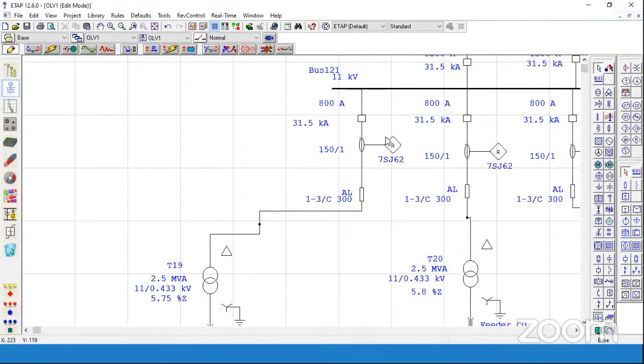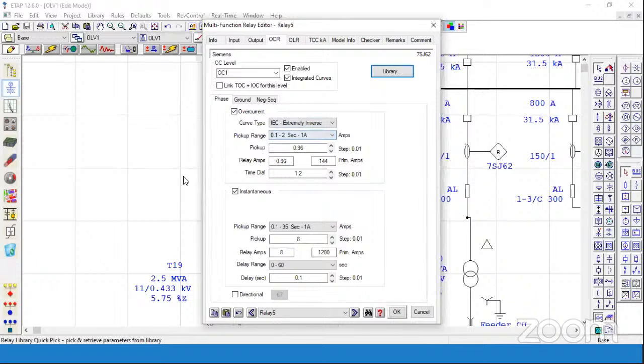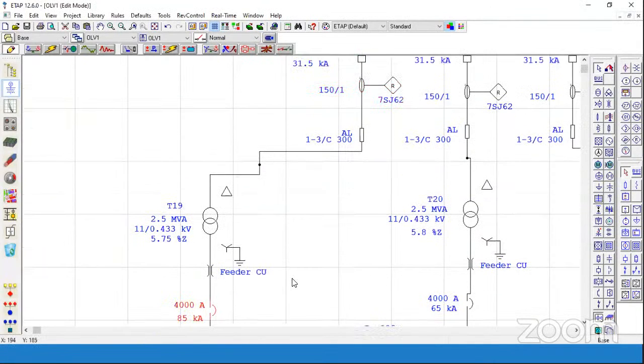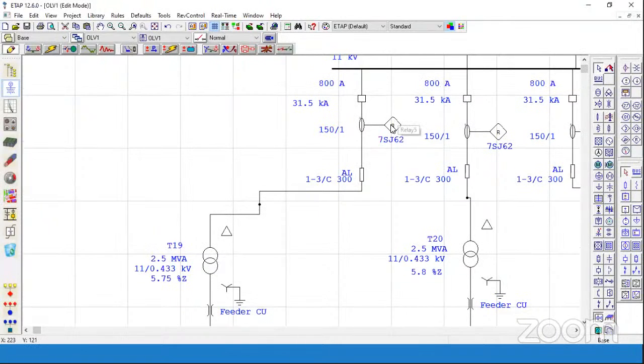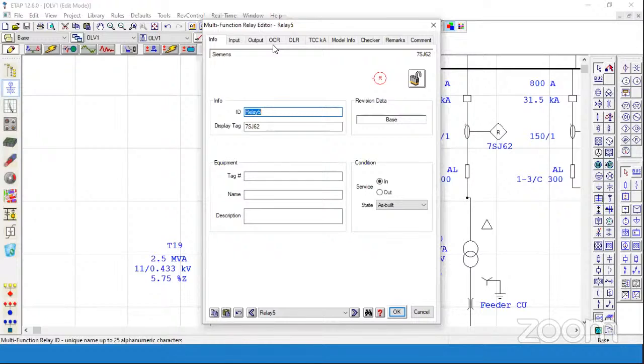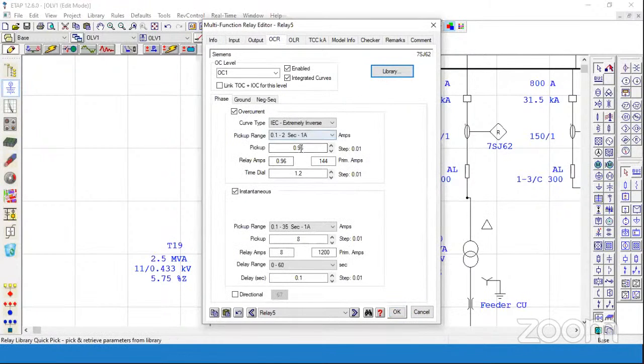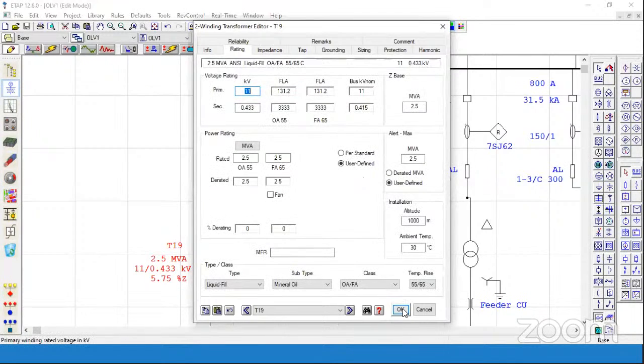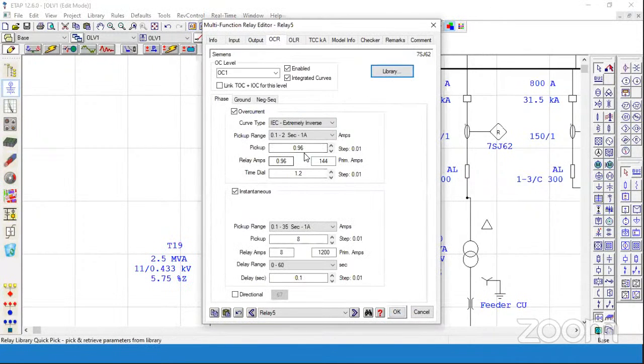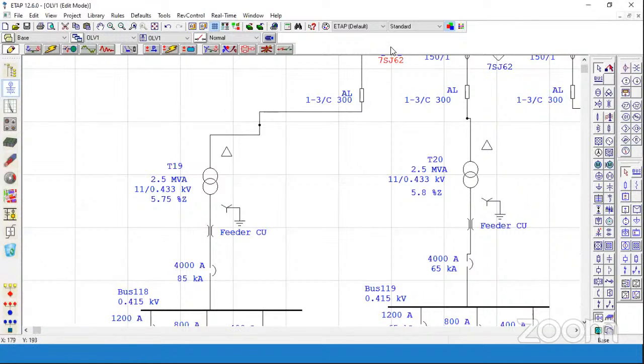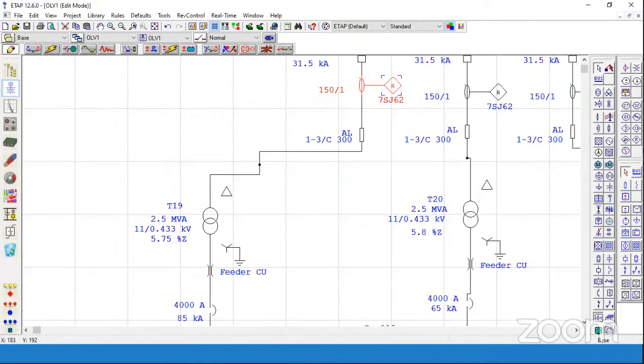Now we will go for this relay. The relay is set in such a way that its curve should match with the circuit breaker of the LV section, and it should be able to withstand any fault current in the downstream network. The primary ampere which we have taken into consideration is 131, and with 10% of that, the relay has been set to 144 ampere, with a time grading margin of 300 milliseconds, as backup protection for this particular fault. I will show you here how I have calculated this.